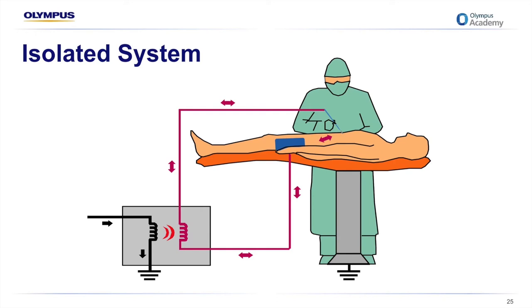This type of generator significantly reduces the patient's risk for an alternate site burn, secondary to current diversion, because the current is referenced back to the generator. If such generators are not equipped with a contact quality monitoring system, a burn at the return electrode site may occur because of insufficient return electrode contact or conductivity.